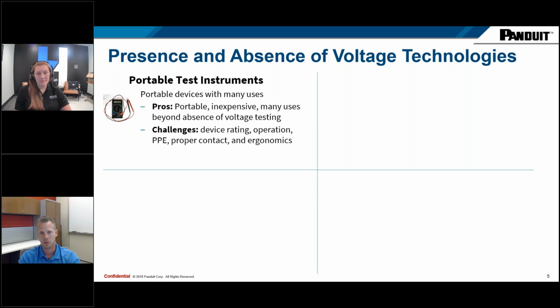Challenges, as Caitlyn pointed out: device rating, operation, stuff to use, PPE, making proper contact, ergonomics of them. There's a lot of human error, a lot of choices that you need to make that go into using that device. They're great for presence of voltage testing and absence of voltage testing, because you can go through that process to ensure that they are functioning properly. So the only reason absence of voltage testing is really great for those is because you can use those devices to go through that live-dead-live process.